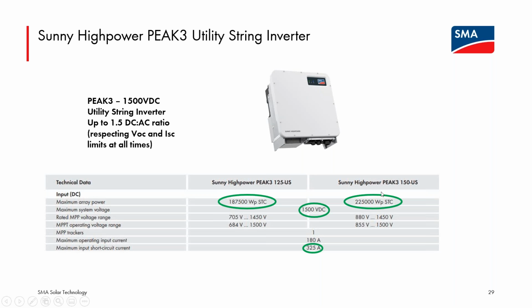Down here, I just want to comment on my point that these units really should be working with arrays that are strung out to 1500 volts. For the 150 kilowatt unit, that's an almost have-to-have. Again, the MPPT operating voltage range goes down to 855 and then all the way up to 1500. But if you try to work this inverter with an array that was limited to 1000 volts or less, I think you would have very poor behavior from that system. So these really should be considered 1500 volt array machines only.